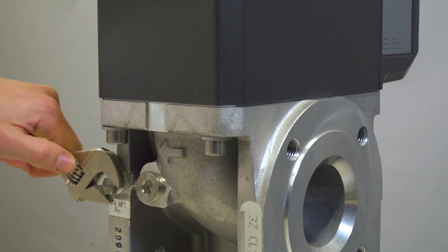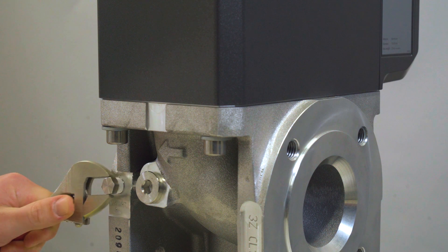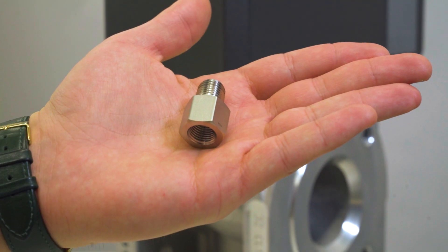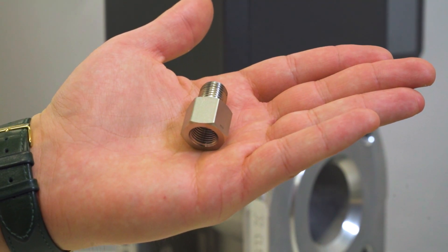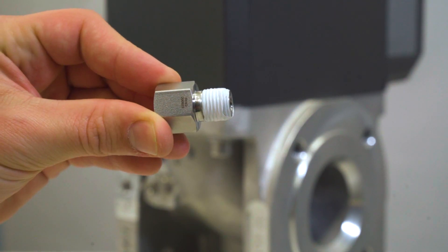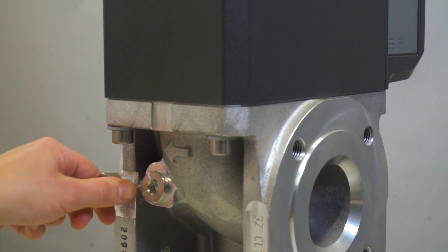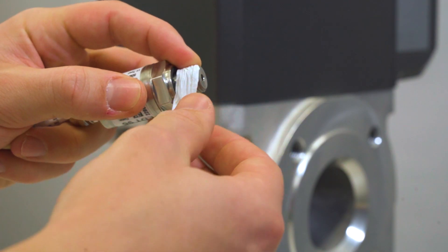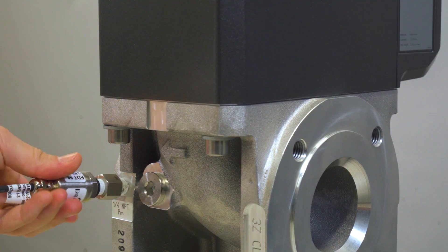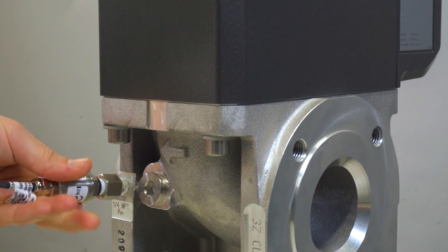Therefore, we will remove the dummy plug at the position of the external pressure sensor, which is marked on the adapter with the sign PM. If necessary, and your meter has got an NPT 1/4 inch thread type, you will require an adapter to change the thread type to G¼ inch. Please keep in mind to wrap PTFE tape around the threads to ensure proper tightness. After that, you can start to screw in the external pressure sensor to its intended position.